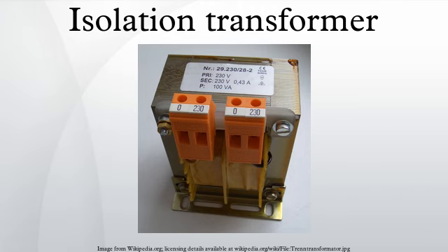Electrical isolation is considered to be particularly important on medical equipment, and special standards apply. Often the system must additionally be designed so that fault conditions do not interrupt power, but generate a warning. Supply of equipment at elevated potentials: isolation transformers are also used for the power supply of devices not at ground potential. An example is the Austin transformer for the power supply of air traffic obstacle warning lamps on radio antenna masts.